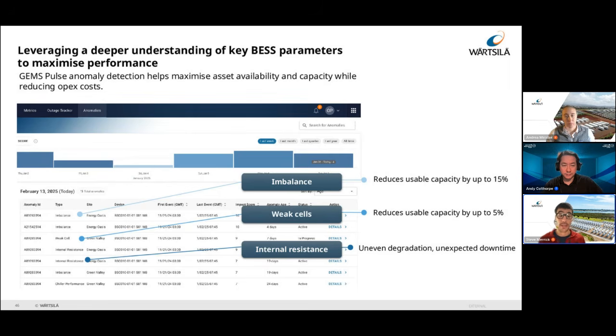Another example is internal resistance. This can result in uneven currents between strings, and eventually, if it goes on long enough, that can result in uneven degradation. If the gap gets wide enough, one of the strings can actually trip offline and you might get an outage, which we want to prevent. So the aim is to identify this emerging trend before it impacts the system level.